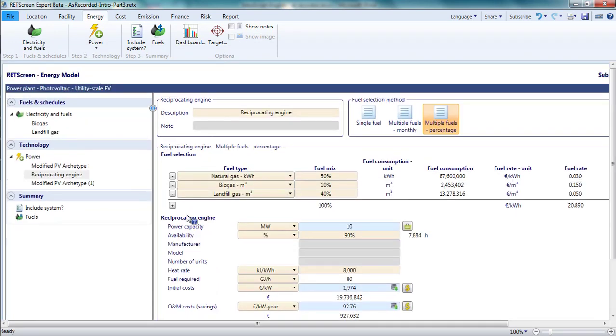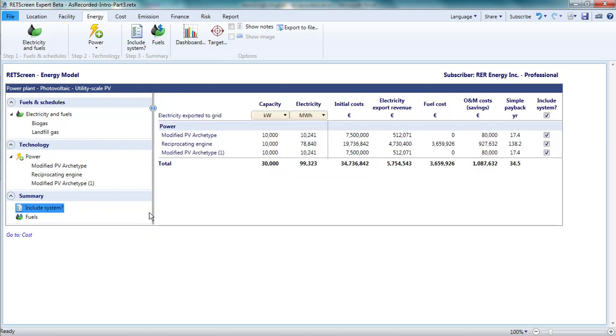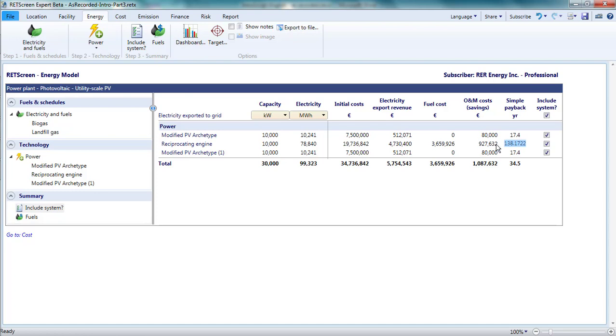Back in the include system table, I can compare these three projects, the two identical PV systems and the reciprocating engine. The reciprocating engine has the highest revenues but also the highest costs and has a very long simple payback. Note that revenues, O&M costs, and fuel costs are reported on an annual basis.